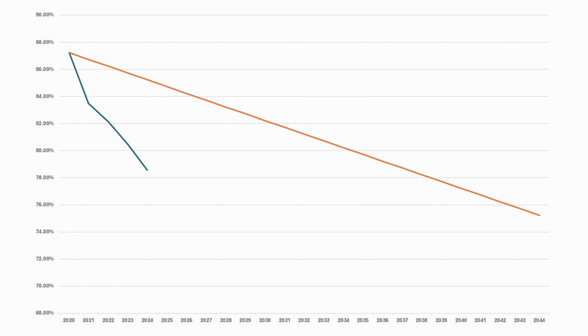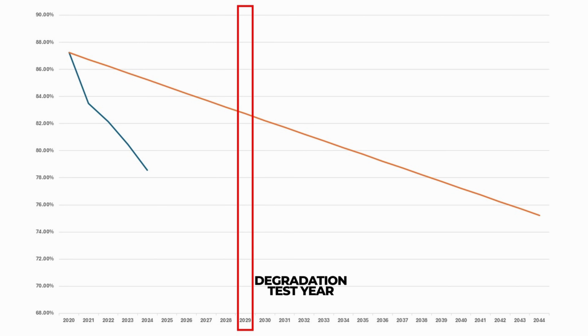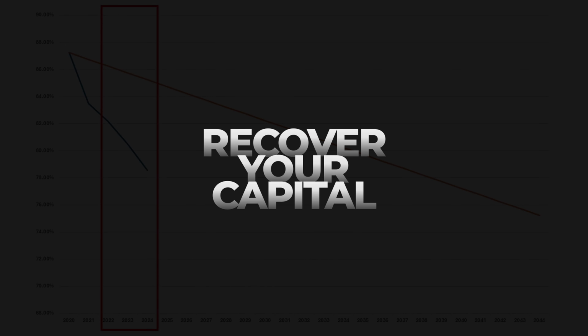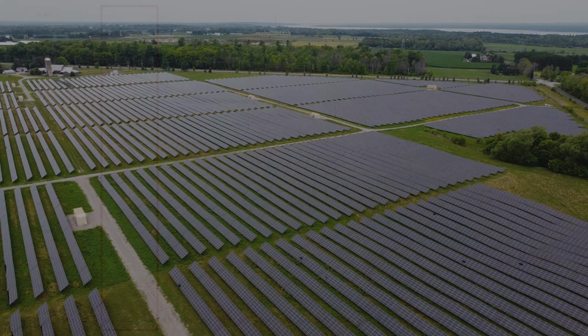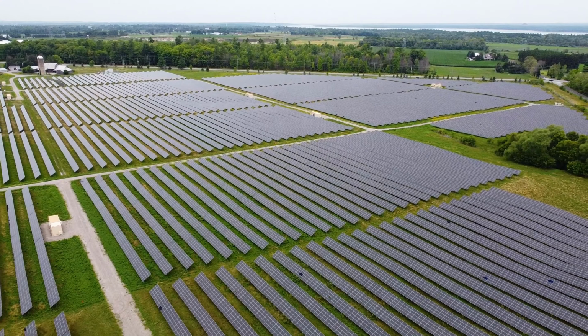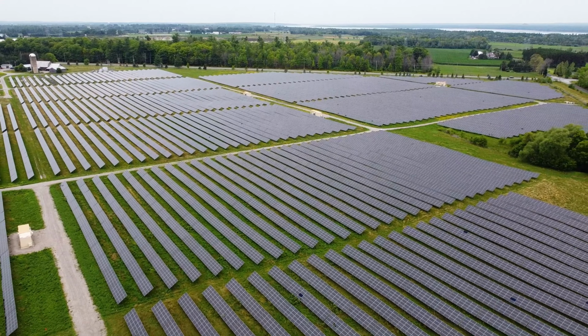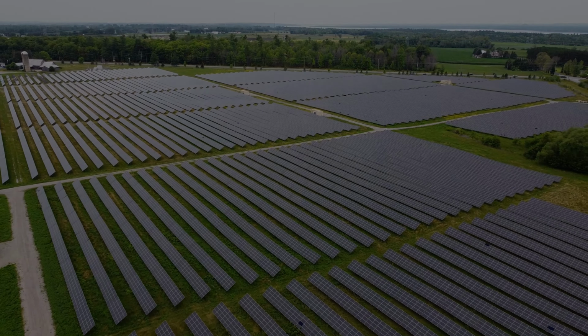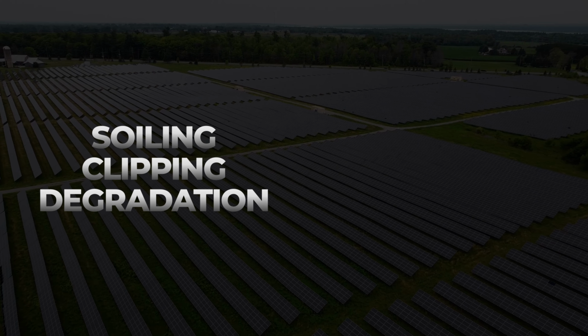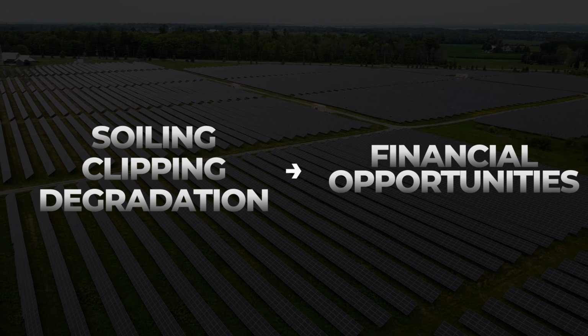We don't wait a decade for a degradation test. With continuous PR monitoring, we can identify abnormal decay by year 3 or 4 and initiate warranty claims early, recovering capital before losses compound. Closing the degradation gap is what protects investors' long-term capital. When we quantify discrepancies from soiling to clipping to degradation drift, we turn them into financial opportunities.